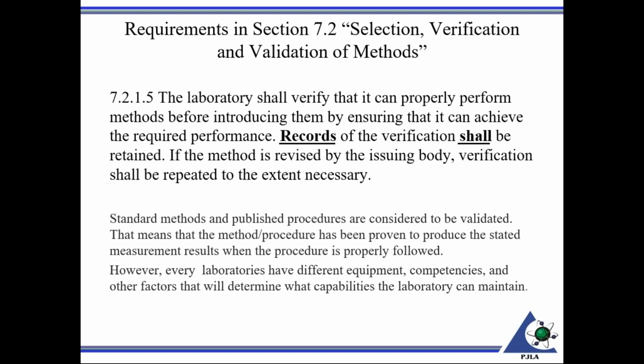So once again, standard methods and published procedures are considered to be sufficiently validated. That means that the method procedure has been proven to produce the stated measurement results when the procedure is properly followed. However, every laboratory has different equipment, competencies, and other factors that will determine what capabilities the laboratory can maintain.